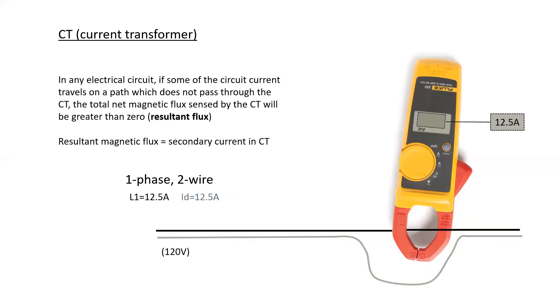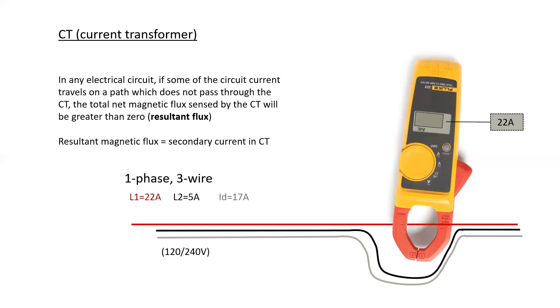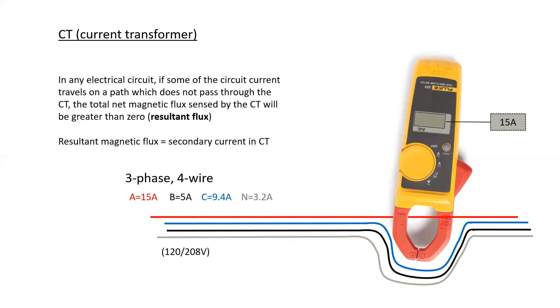Things change when we only have one conductor. And that's how we obviously utilize our clamp ammeters. If some of the circuit current travels on a path which does not pass through the CT, the total net magnetic flux sensed by the CT will be greater than zero. And so we'd call that as resultant flux.